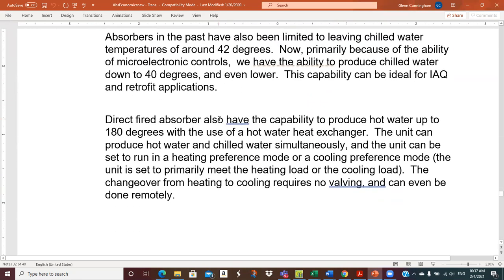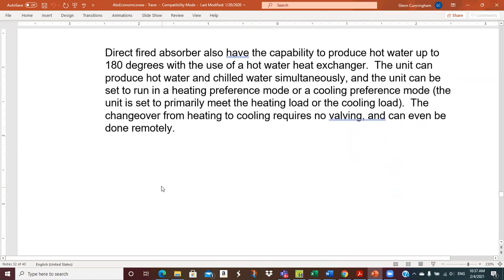Direct fire absorber has the capacity to make up to 180-degree hot water, which of course we can use for heating or space heating or whatever. And the changeover from heating to cooling requires no valving. It can even be done remotely. So that's a nice feature.